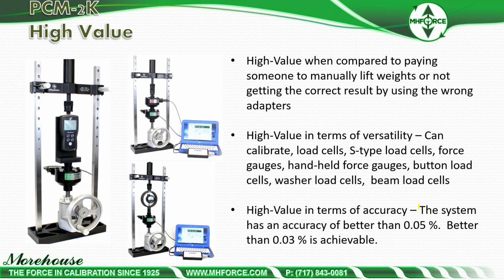Now you have to be careful down here. This often requires multiple load cells. There's manufacturers out there that spec these accuracies, and they'll say something like, "Hey, my system is accurate to 0.05." So when we say our system is accurate to 0.05, that often means that it's accurate to like 0.03% at full scale. I didn't put full scale in there. People write a full scale. Well, full scale is really difficult accuracy wise, because there's a number of factors when you start looking at uncertainty to go in.